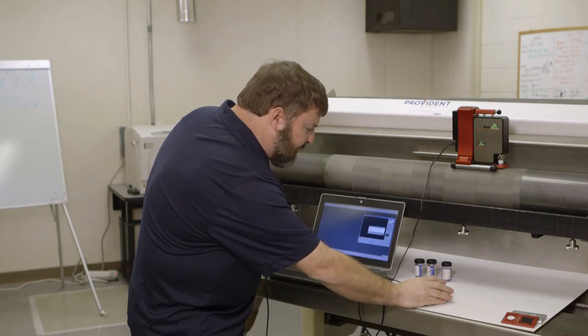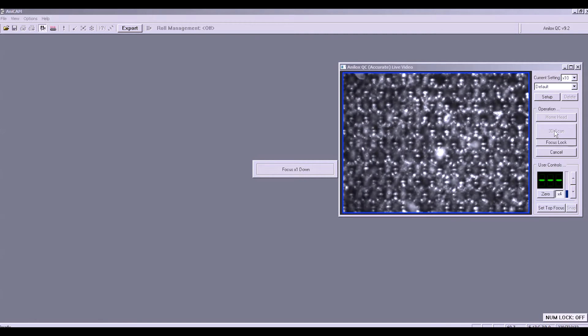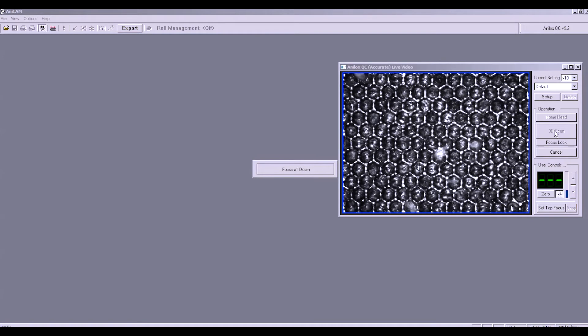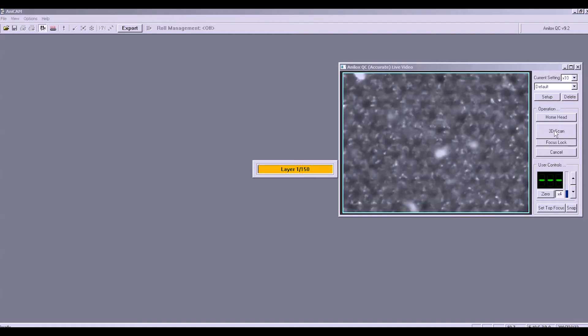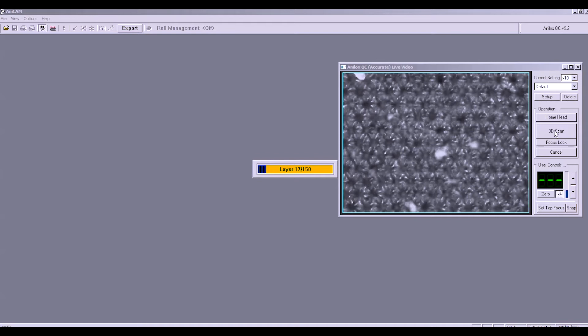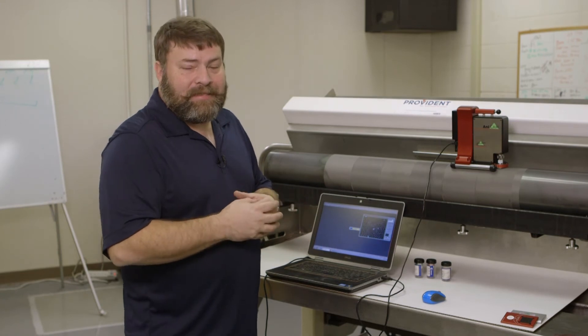Once that's done, I just press 3D scan. What the unit is doing at this point is it's actually going to find its focus based off of what you told it. It's going to adjust the lighting. And once it starts, it's going to take a picture and then move down one micron and take another picture. And it's going to do that for 150 times. So it captures a picture every micron from the top of the cell to the bottom of the cell. This whole process takes about 60 seconds.